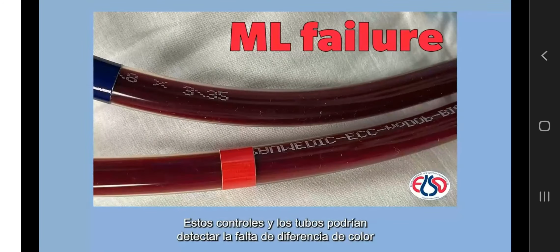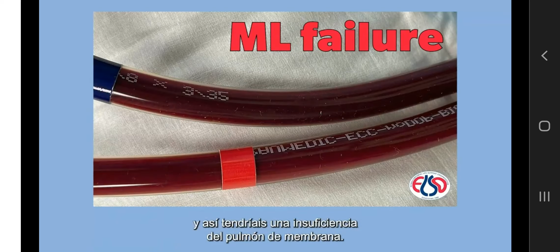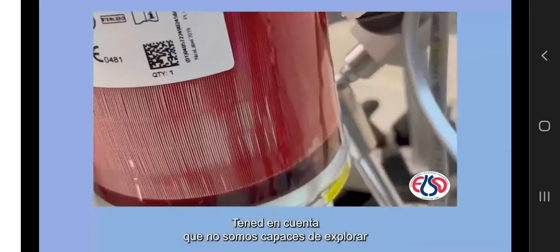Visual control of the tubing could detect the lack of color difference between the blood entering and the blood exiting the membrane lung when you have a membrane lung failure. With the so-called flashlight test, transilluminating the device, you could see fibrin strands, clots and thrombi. The more common locations of thrombi and clots usually depend on the flow dynamics of the specific device. Assess the extension and the location of this phenomenon. Consider that we are not able to explore the deeper structures with the flashlight test.